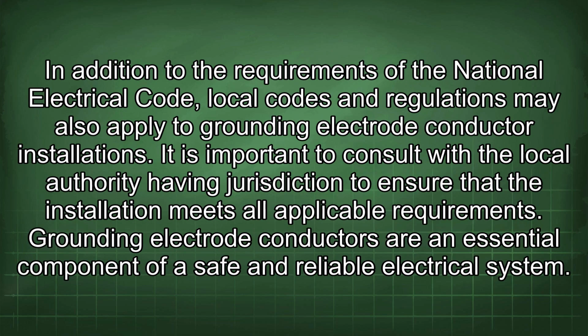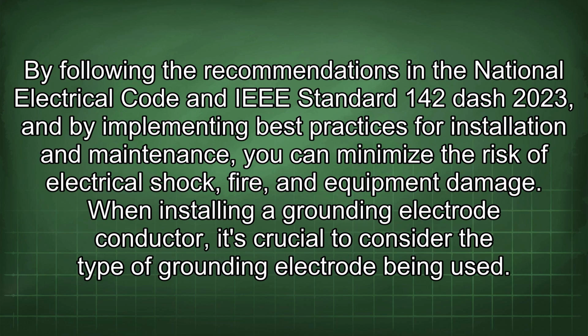In addition to the requirements of the National Electrical Code, local codes and regulations may also apply to grounding electrode conductor installations. It is important to consult with the local authority having jurisdiction to ensure that the installation meets all applicable requirements. Grounding electrode conductors are an essential component of a safe and reliable electrical system. By following the recommendations in the National Electrical Code and IEEE Standard 142-2023, and by implementing best practices for installation and maintenance, you can minimize the risk of electrical shock, fire, and equipment damage.